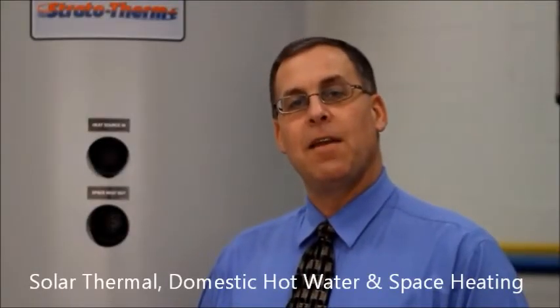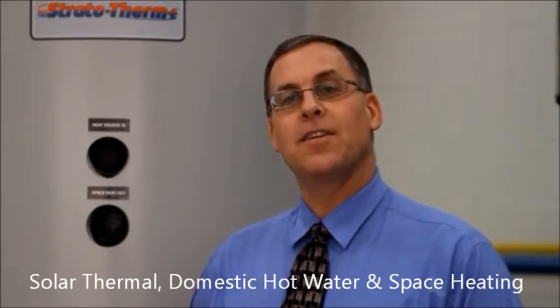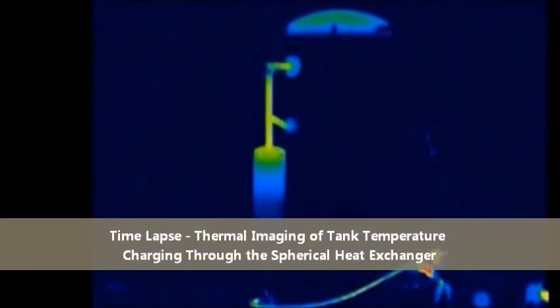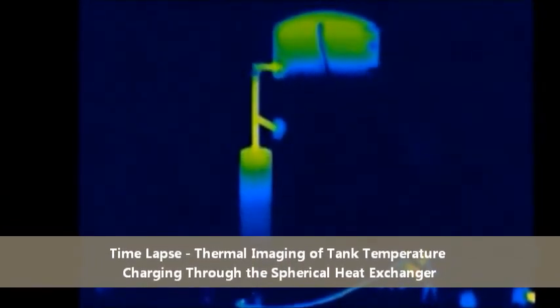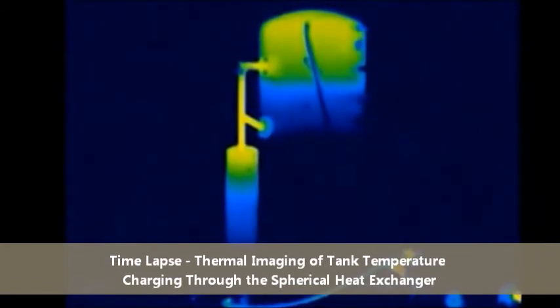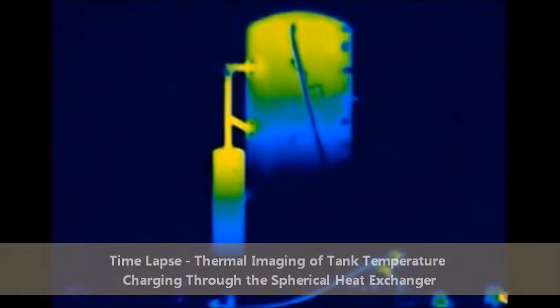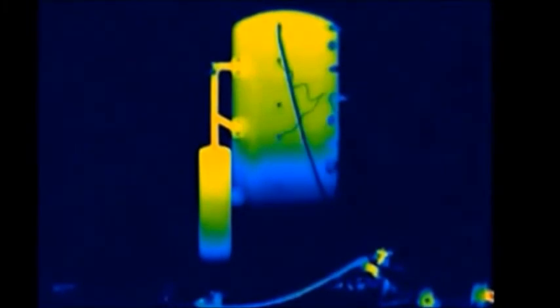I see. So this product ties the three different systems together, that being solar thermal, domestic hot water, and space heating. So Jeff, what I'm hearing is stratification is very valuable to the performance of this product. Can we dig a little deeper and talk about stratification and the benefits that it brings to the table? Well, Stratotherm Plus, as the name implies, is indicative of stratification. This is an important design aspect of this product. Without the need of an additional circulator, the design relies on the natural buoyancy of hot water to rise to the top of the tank, and this also allows the coolest water to fall to the bottom of the tank, or stratify. Let's take a look at how the stratification plays into the three different functions of this tank.